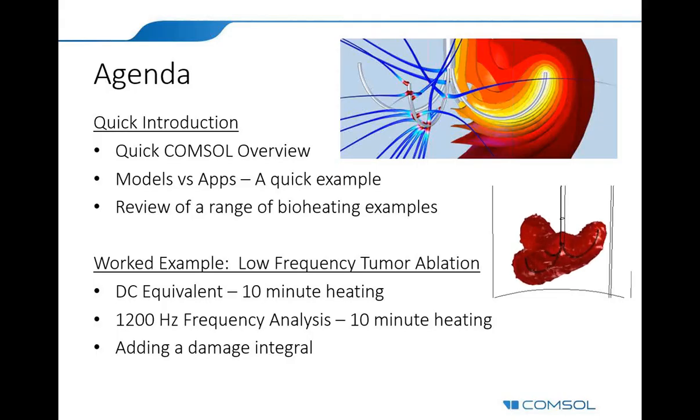Now, as you folks in the industry know, RF tumor ablation can be, well, it spans a wide range of frequencies. For those of us that think in engineering terms, frequently we'll think, well, if you're talking about RF, you're talking about Maxwell's equations using wave analysis. We can do that. In fact, later in the webinar, I'll show you a couple of examples of that. But the industry also uses that for what I would think of as fairly low frequency things.